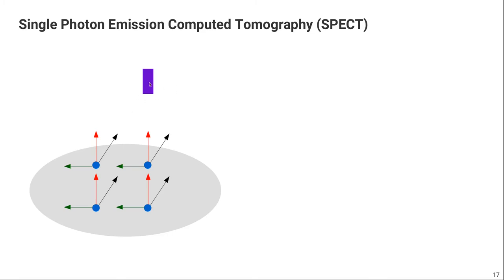And if you look at that arrangement, you can actually see, unfortunately, there is no angular information in the detected events. This detector will see photons coming from all directions. So it will see the red photons coming from that emission point, but also the black photons from that emission point. So if you simply do that, we don't acquire a projection.